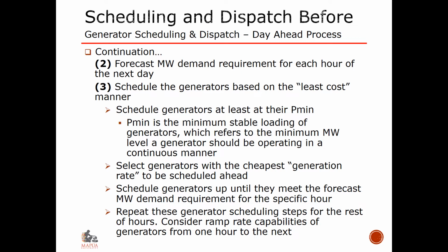That's your maximum capacity. Now, out of the 14,000, let's say I have a PMIN of 5,000, let's say 6,000 megawatts. Now, that already covers that 6,000 megawatts I have to schedule. So, out of the 10,000, I'm already committing 6,000 megawatts because they're PMIN. I cannot schedule a generator below their PMIN. Now, once I have that 6,000, I only have the remaining 4,000 megawatts to schedule, right?